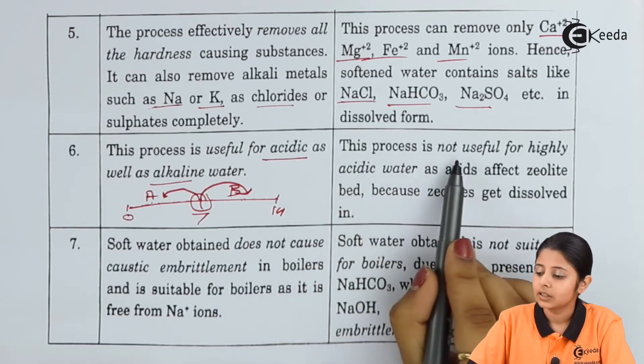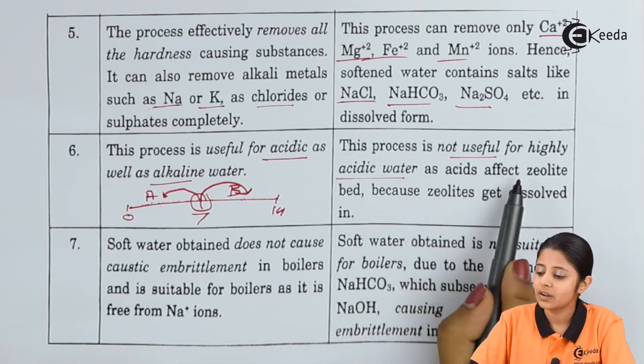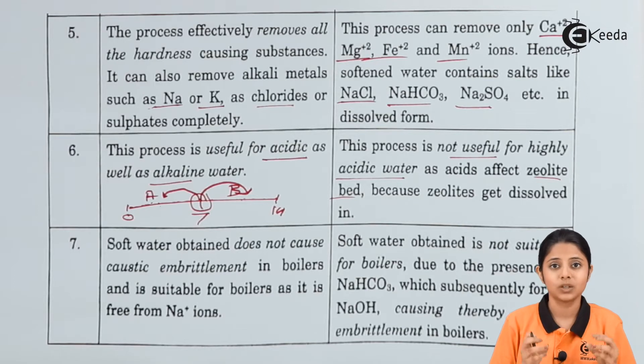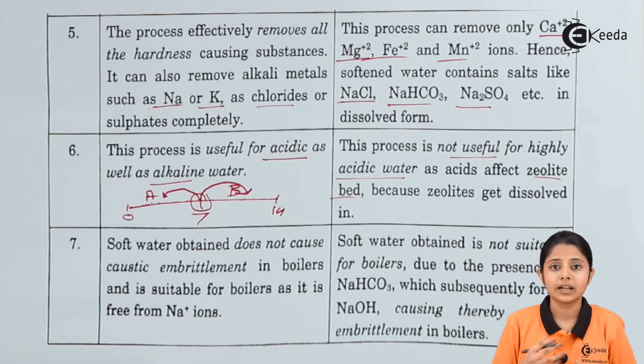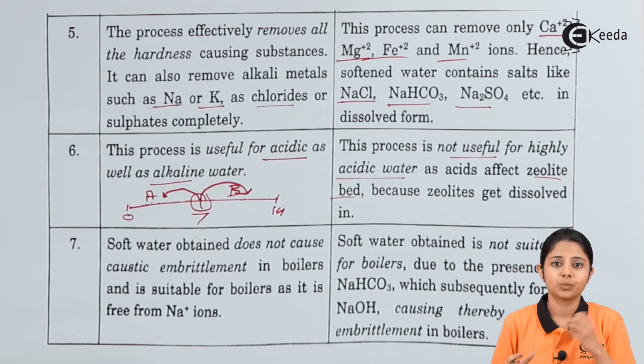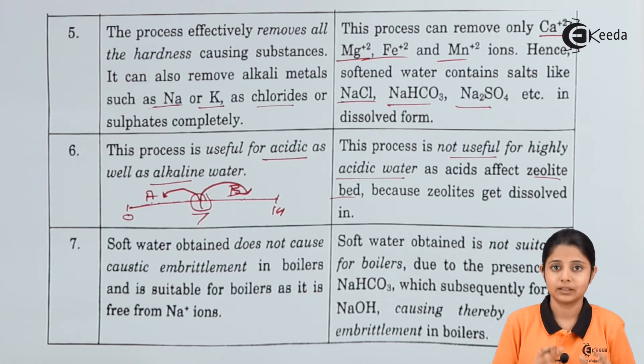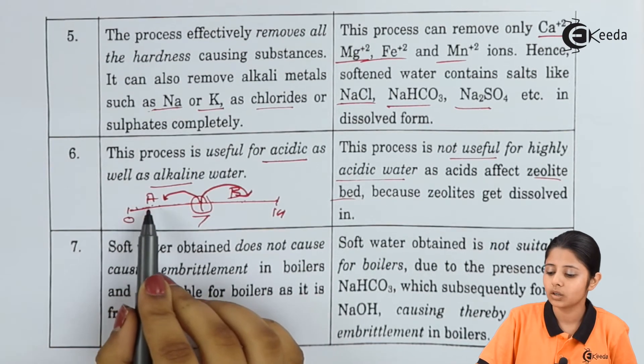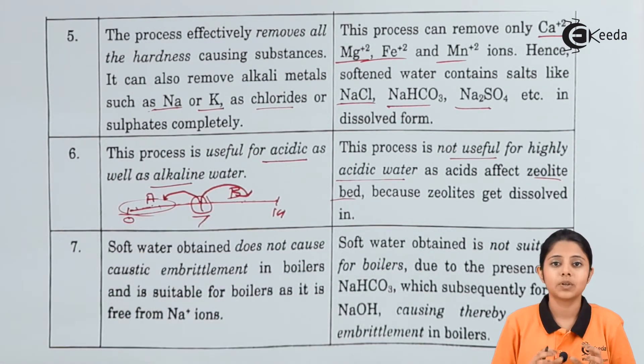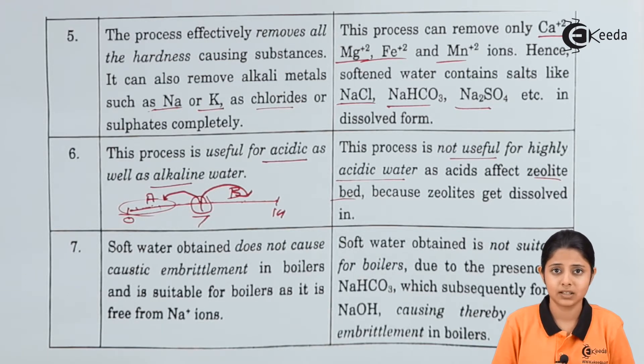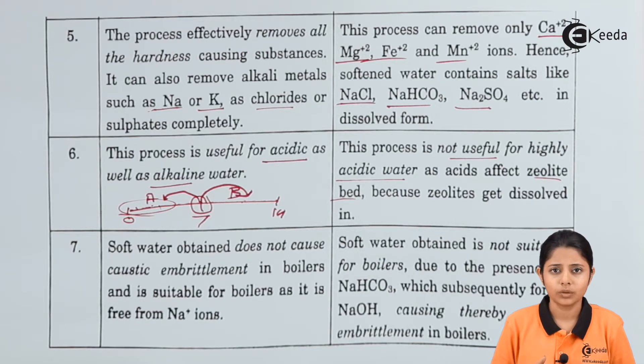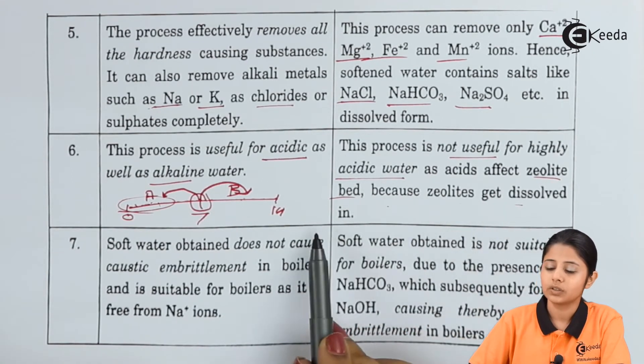For the zeolite process, it is not useful for highly acidic water because acid affects the zeolite bed. The zeolite (also called permutite) is added to the water to react with impurities and form precipitates that are later removed. However, if the water is highly acidic — in the pH range of 0 to 3 — the zeolite process cannot be used, because zeolite undergoes different reactions with highly acidic substances, loses its properties, and can itself contaminate the water further, as zeolites dissolve in strong acids.